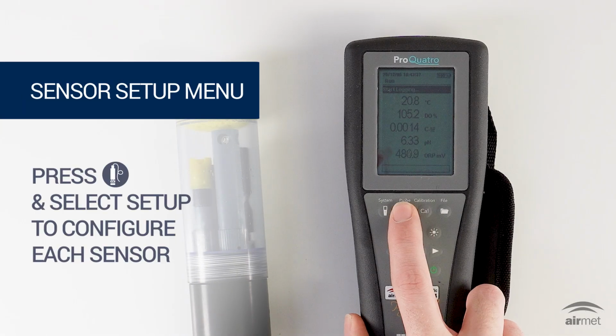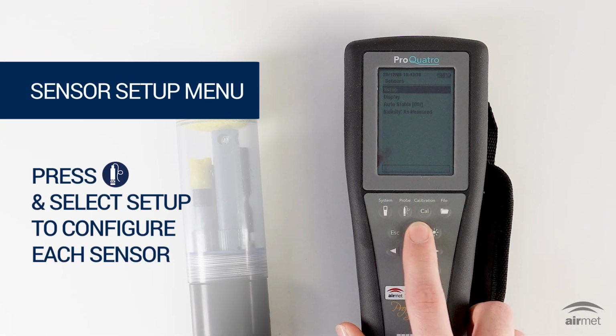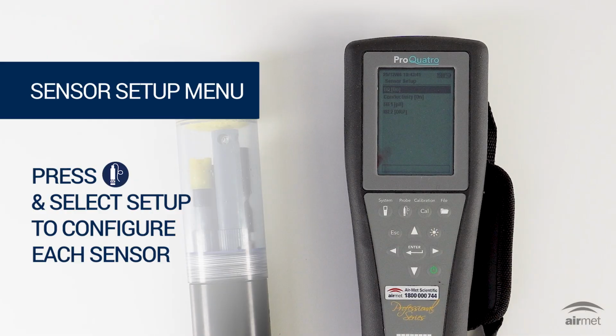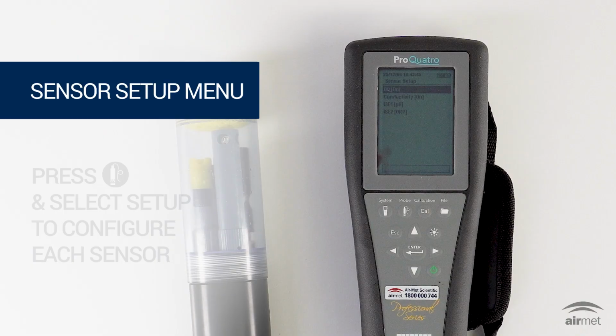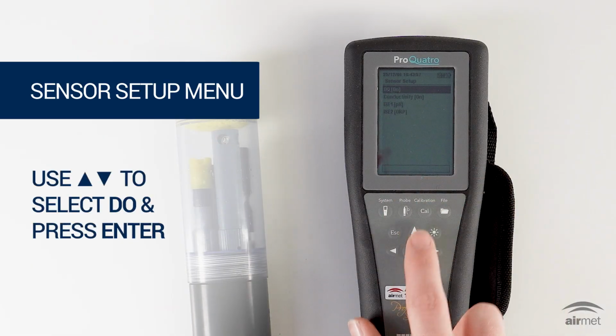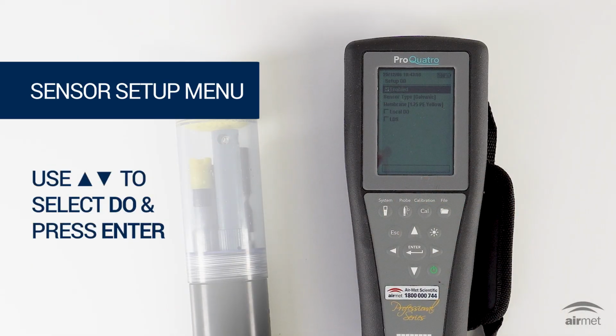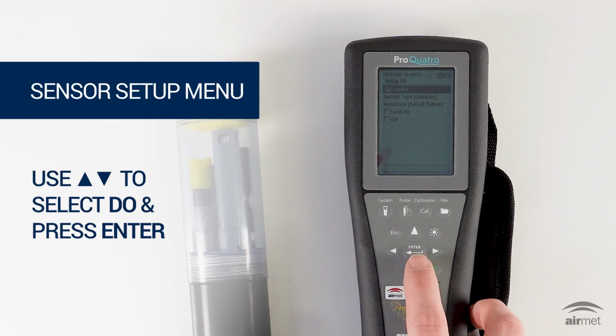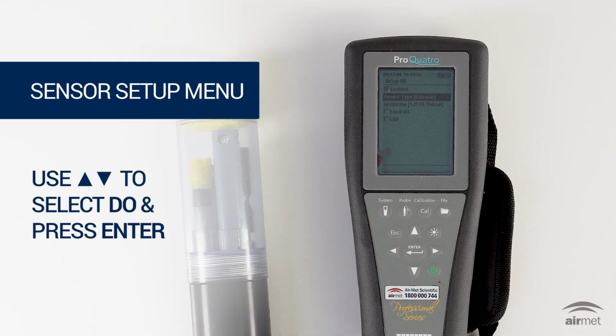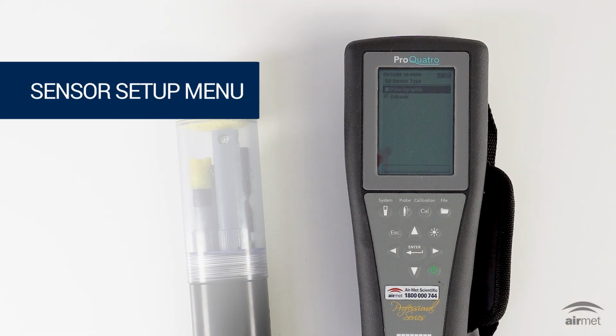The setup menu allows you to configure each installed sensor by selecting its measurement type, specifying the membrane used, and enabling or disabling parameters. To configure the dissolved oxygen sensor, highlight DO and press Enter. The instrument supports two DO sensor types depending on the probe installed.